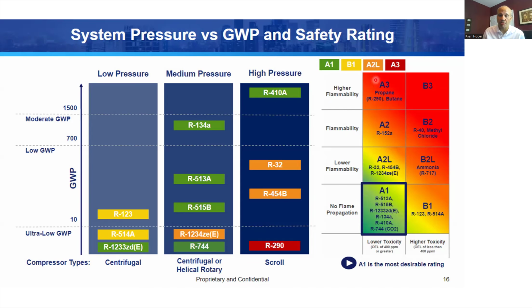The one, two, and three means that it was what most of us would say non-flammable, but technically it is flammable, but we call it no flame propagation, right? For the ones, you can burn R-410A. It is flammable, if you will. But when you take your torch off of it, it'll just go out. It won't propagate the flame. The flame won't spread through it. So you can burn it, but it's not what most people would consider flammable. So that's the ones. Two meant it was flammable, and three meant highly flammable, like propane and butane. You could use them as a fuel if you want to, right?